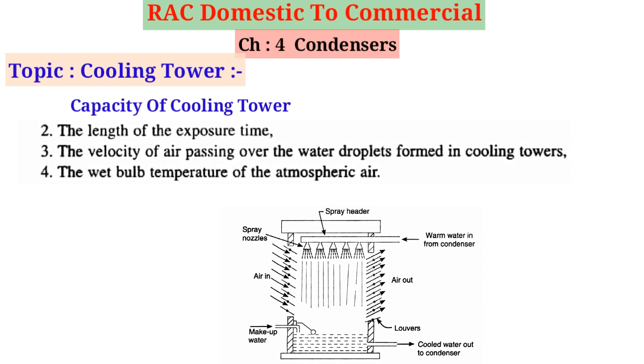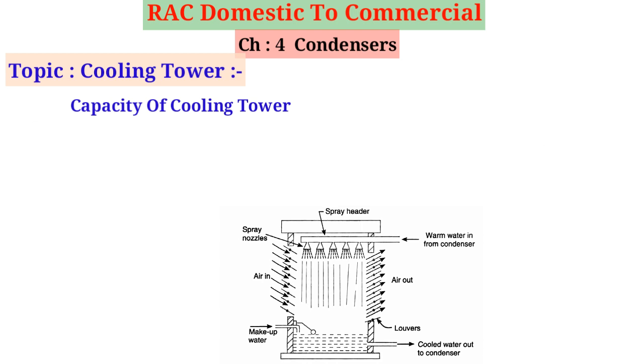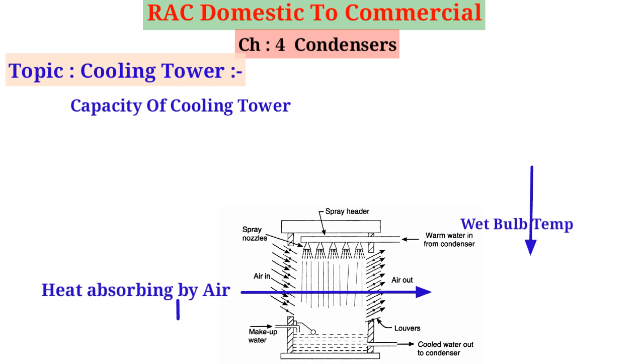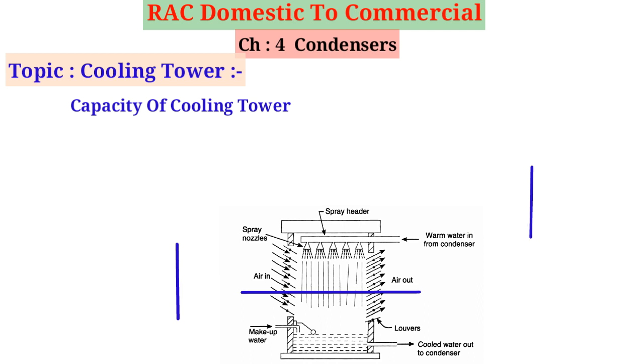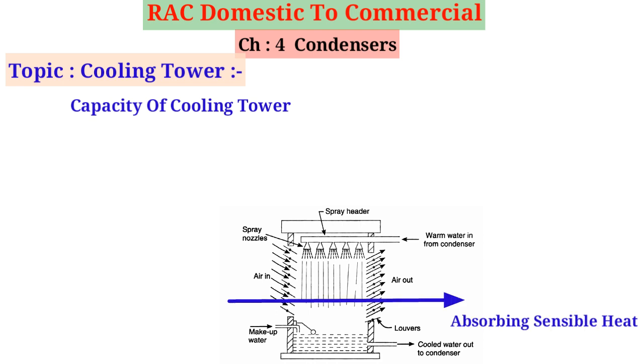4. The wet bulb temperature of the atmospheric air. It may be noted that the capacity of spray ponds increases as the wet bulb temperature of air decreases. 5. The dry bulb temperature of air has less influence on capacity because air absorbs little sensible heat from water. However, the amount of sensible heat the air can absorb increases as the dry bulb temperature difference between the water and air increases.